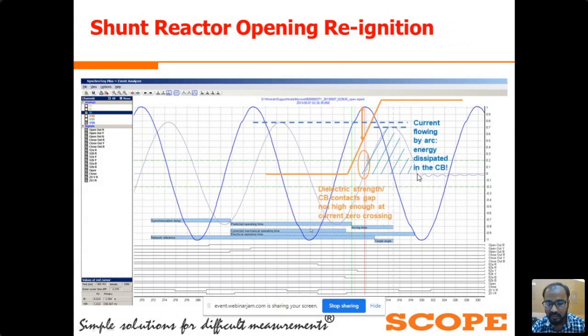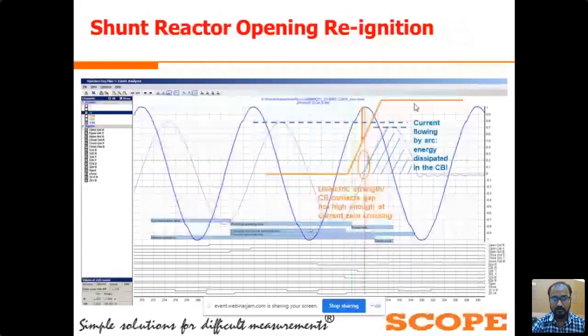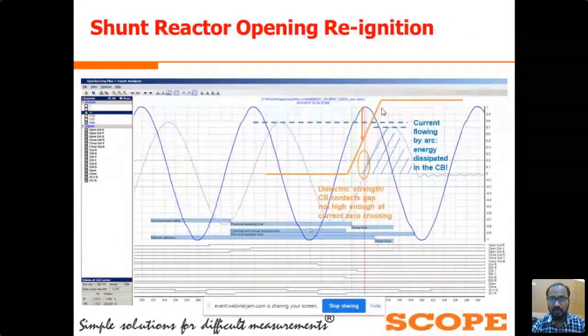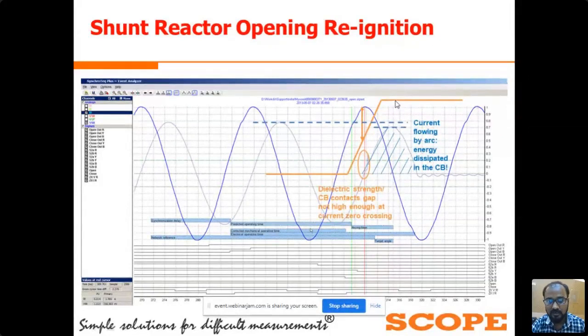At this point we can see the dielectric strength between the CB contacts is more than the system voltage. Here we can see the dielectric strength between the CB contacts is more than the system voltage. So due to that, from this point we have observed no reignition of system current.